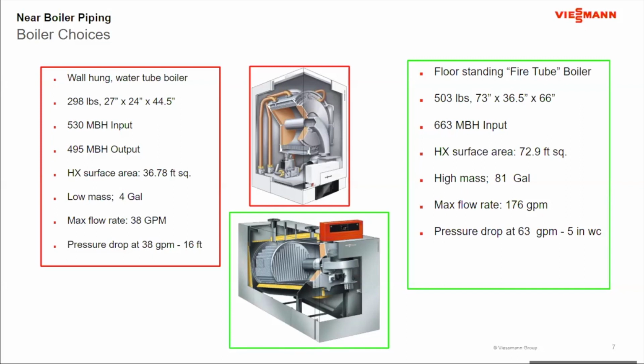So for this floor standing boiler, the heat exchanger surface area is 72.9 square feet. It's high mass. It has 81 gallons of water inside the boiler. Its max flow rate is 176 gallons per minute, and its pressure drop at 63 gallons a minute is 5 inches of water column. So really a lot different style of boiler, but again, both of these boilers are condensing boilers, so they're trying to achieve the same thing.